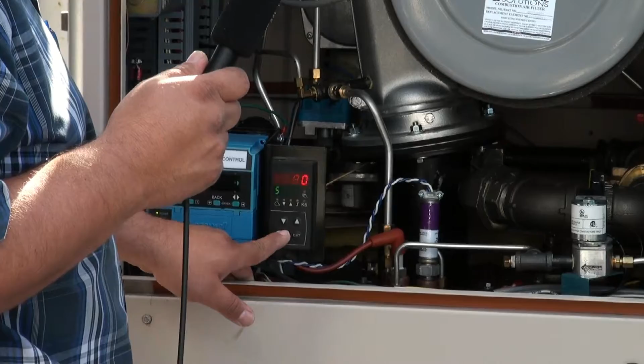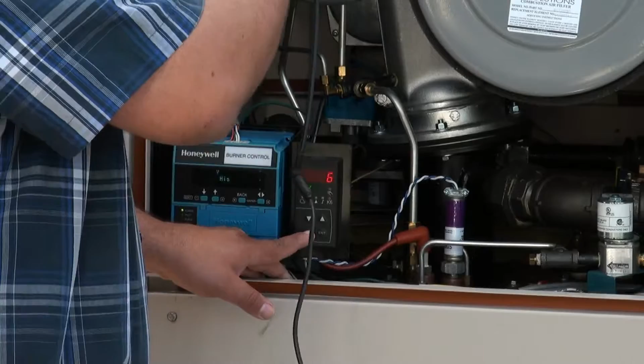These are all set points from the factory. They're just set points that allow the boiler to handle what's going on with the burner, what's going on with the VFD. Those are like your set points for the PID loops and stuff that the boiler's handling. So those stay, you don't change them, they just stay where they're at.